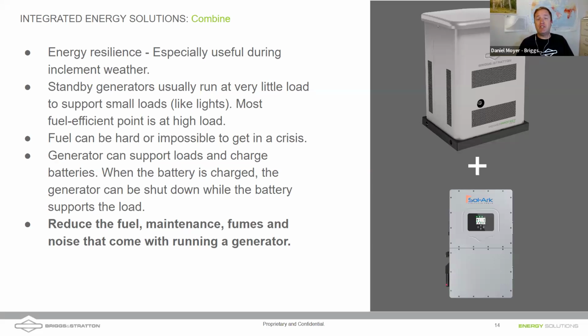With the generator, it's just sitting there waiting for an outage. With an energy storage system, it can be what I like to call a grid interactive appliance, which can accommodate time of use. If you are in certain jurisdictions that don't have net metering, where it doesn't make sense to send solar back to the grid anymore because you're not getting that one-to-one credit, let's store that energy in the batteries and then discharge it at night for the home loads as well.